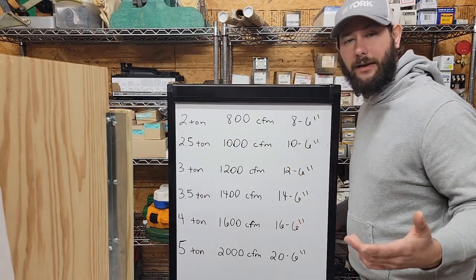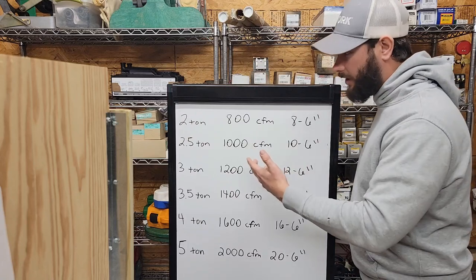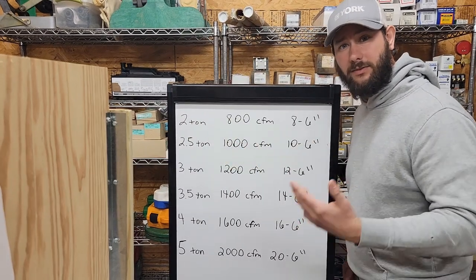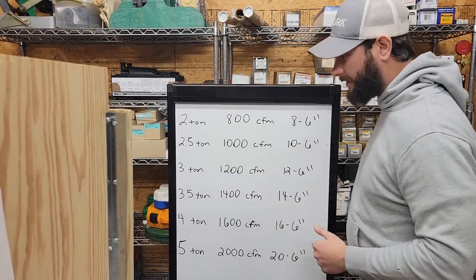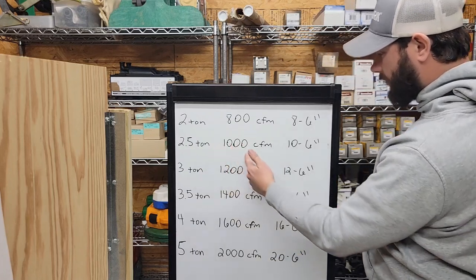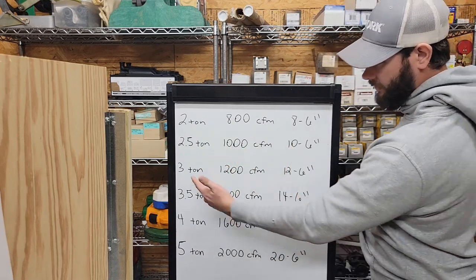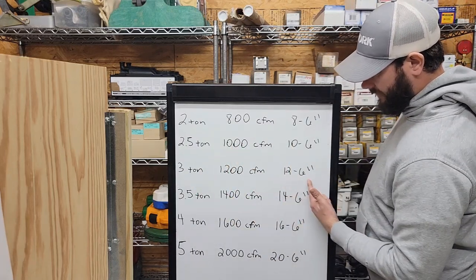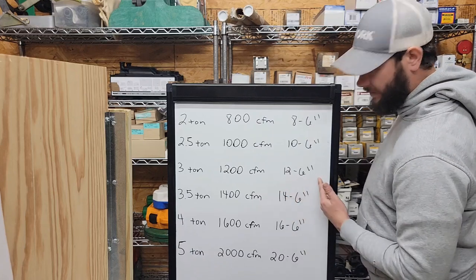My head pressure is going to be out of control. I'm not going to have enough airflow, and that's going to affect my system's efficiency. It's going to affect the capacity. So over here, for 2.5-ton, it's 10, and for 3-ton, 12 6-inch lines, or we could do 6 8-inch lines.